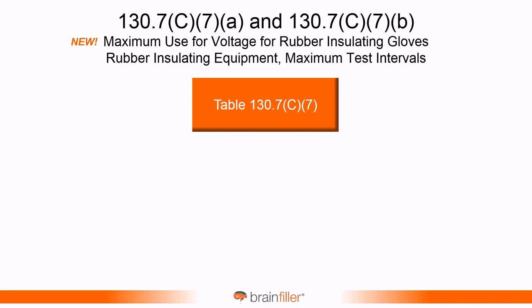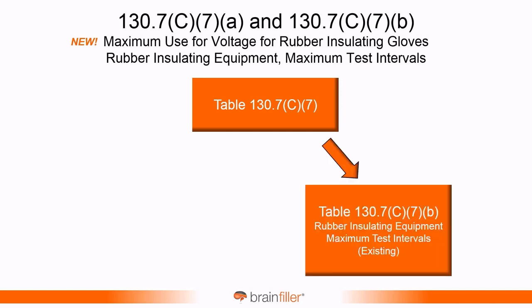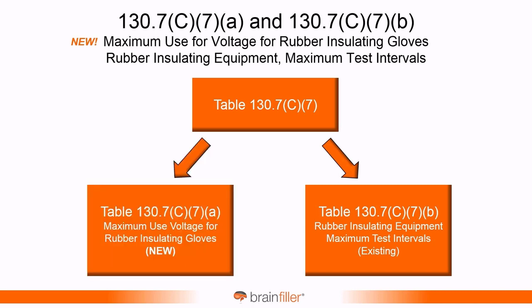Another change to the 2021 edition. We have one table that is now part of a pair of tables. We had table 130.7C7. That was for rubber insulating equipment, the maximum test intervals. That is now 130.7C7B. And we have a new table. That is table A. And table A is for the maximum use voltage for rubber insulated gloves.